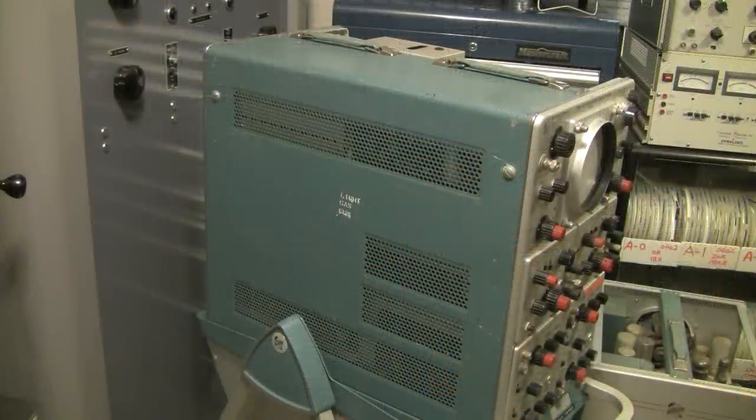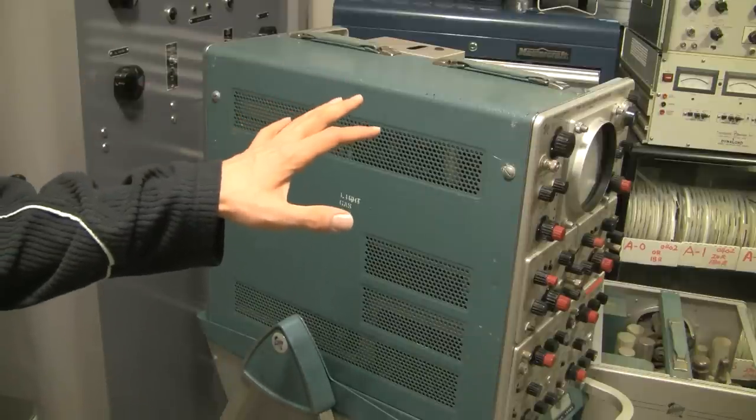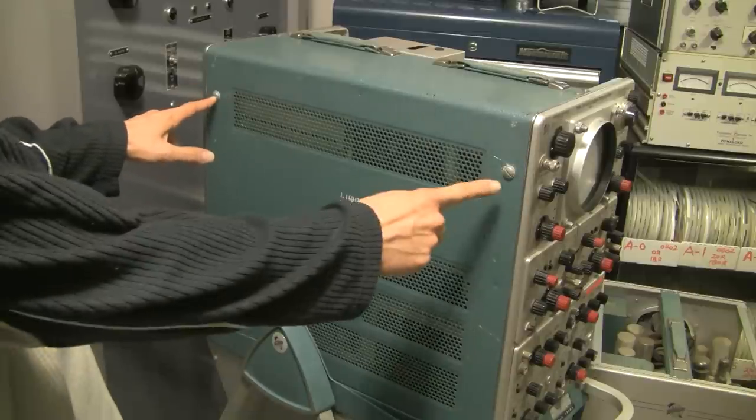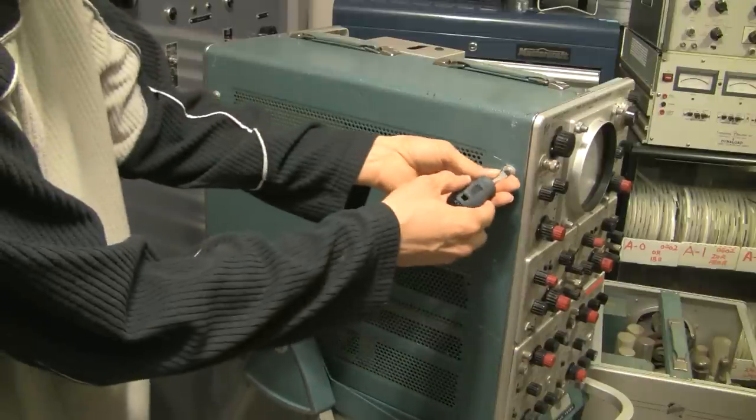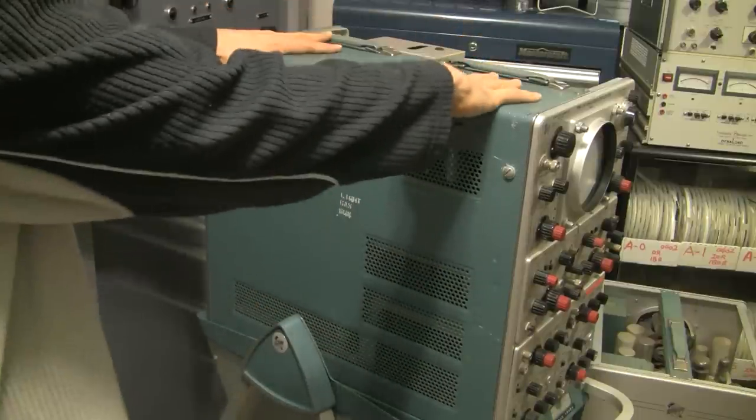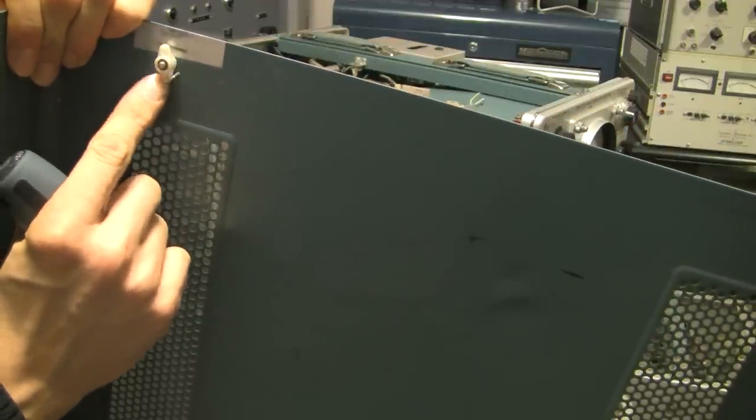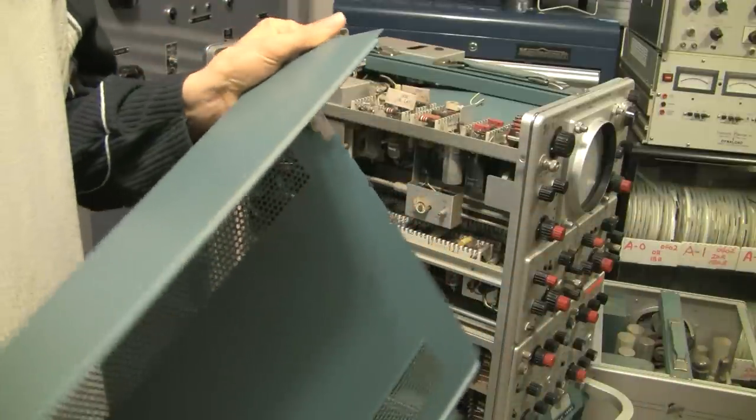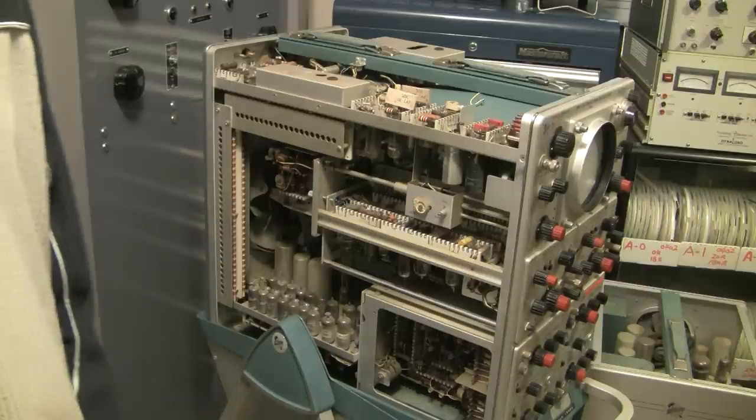Hi. So, here we are looking at the side of the oscilloscope. I've removed all the other sides just to make it a little bit easier and quicker. This one here I've left on so that I can show you how the sides of these scopes come off. They're very easy to get off for quick servicing. We've got these two screws here and all that you need to do is put a screwdriver in there and give it just a bit of a turn. Give it a bit of a turn, put your hands on the top of the case, pull it towards yourself and then lift and the case is off. You can see inside there's just a little nylon nut with a bunch of tangs on it and it hits this piece of the case here and it stops the nut from turning. So, you just need to give it about a turn or so until the nut is loose and then the friction of the screw in the nut will cause it to hit that little tang and then it just loosens off.